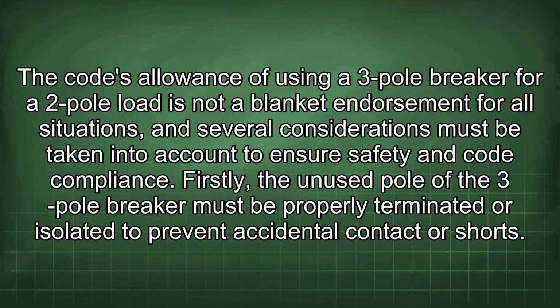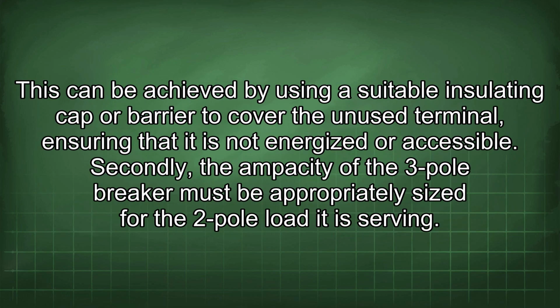endorsement for all situations, and several considerations must be taken into account to ensure safety and code compliance. Firstly, the unused pole of the 3-pole breaker must be properly terminated or isolated to prevent accidental contact or shorts. This can be achieved by using a suitable insulating cap or barrier to cover the unused terminal, ensuring that it is not energized or accessible.